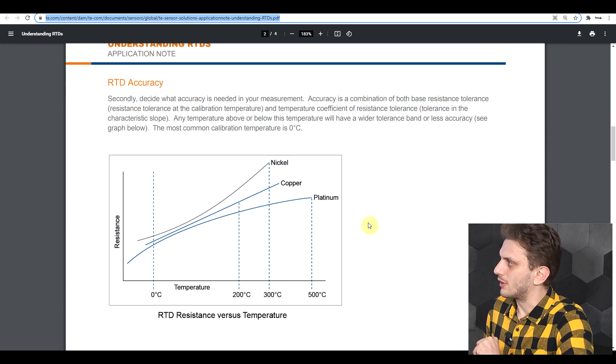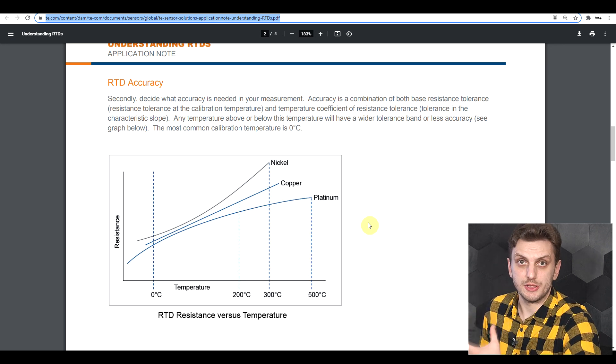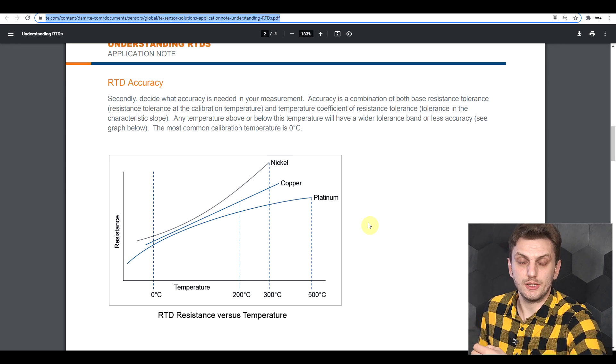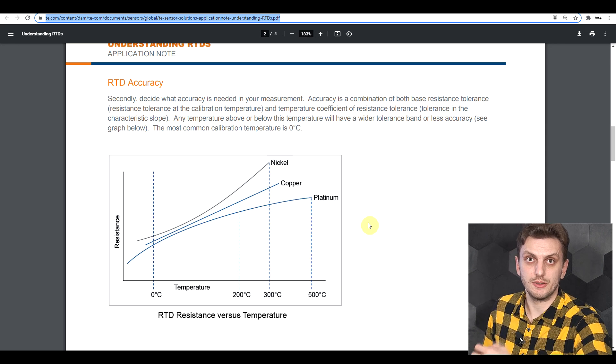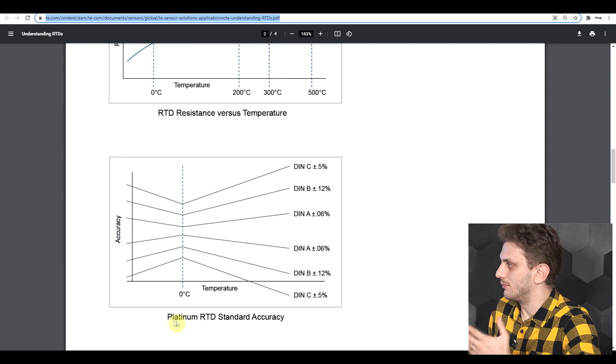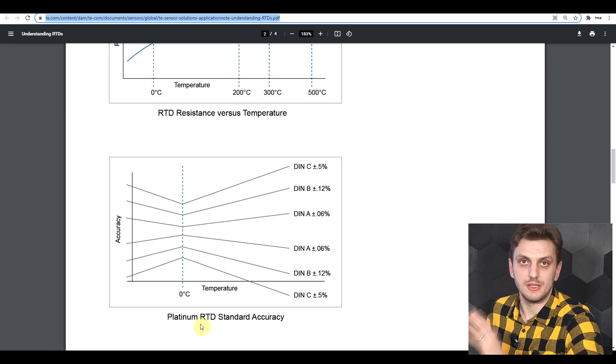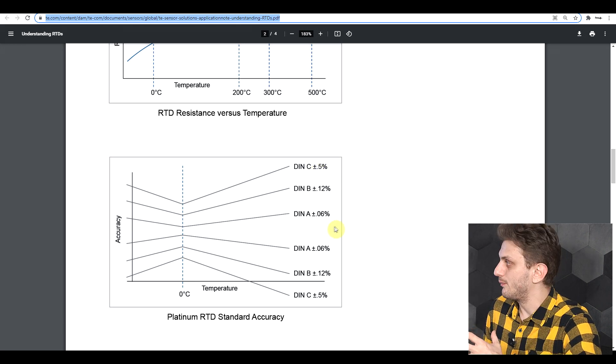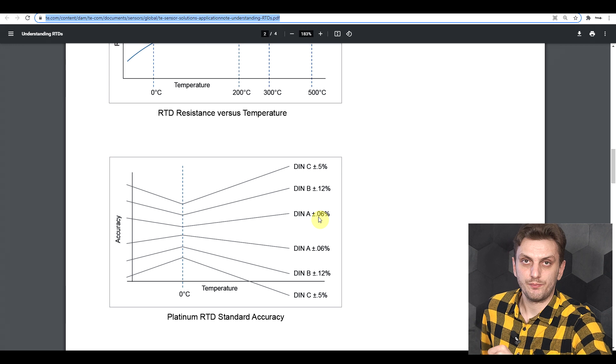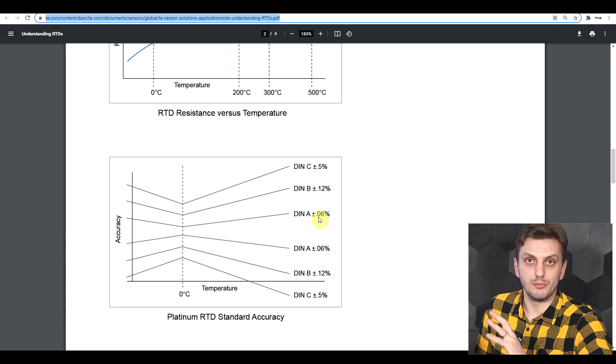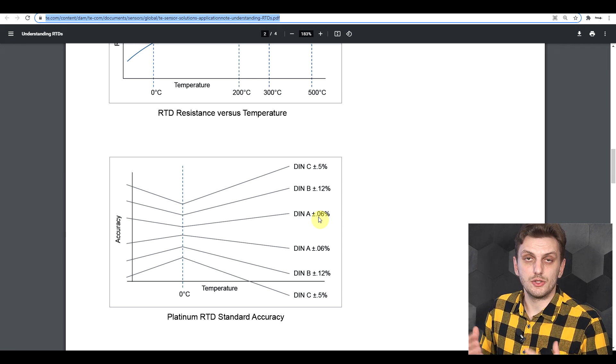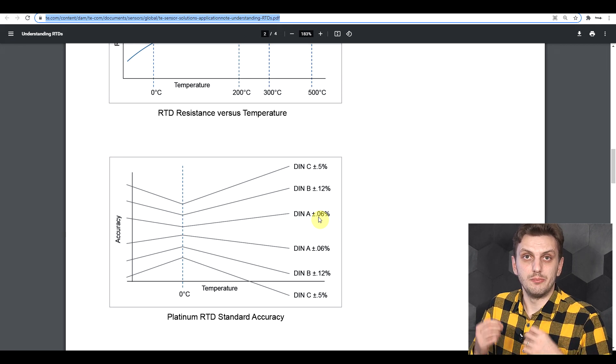The important thing about the RTD is its accuracy and its precision. Compared to the other two methods that we will be looking at today, the RTD is considered the most accurate and precise temperature measurement method. The common accuracy grades listed for your platinum RTD, the most common type of RTD, range from 0.5 percent down to 0.06 percent. This is a completely different ball game compared to the 3 or 5 percent of an NTC.